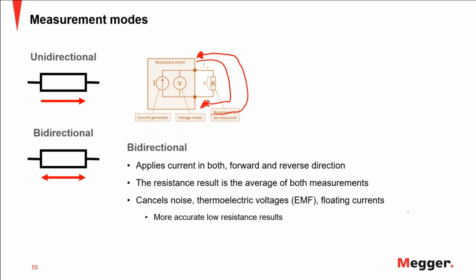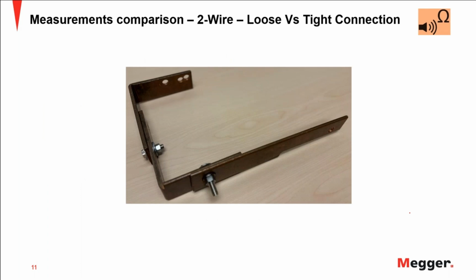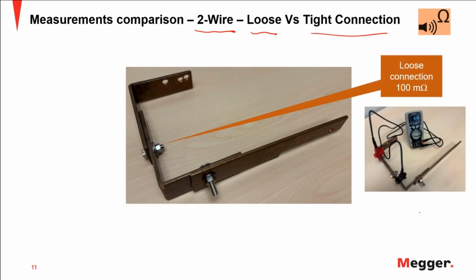So depending on your application, you may want to use unidirectional or bidirectional. It adds a couple of seconds to the measurement, so it's not a big problem to use this method to get more accurate results. So now let's see a couple of comparisons. This first one compares the two-wire measurement on two types of connections, one loose connection and one tight connection. And because it's a two-wire method, we're going to be doing a continuity test here. So this is the loose connection. This is something I did. I tied these with my hands, so no tools.